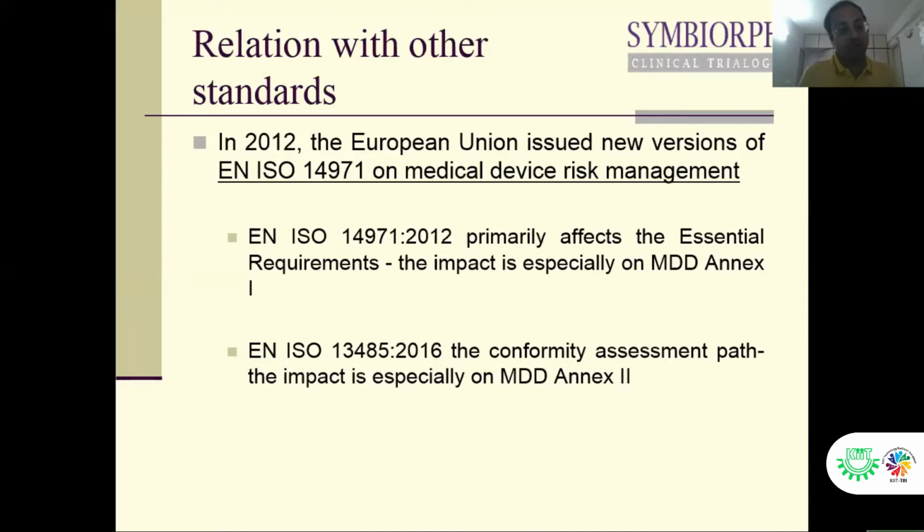And you have to prepare a separate document. You have to see that the risk-based approach on the process and on the product are two separate activities. Here I'm talking about the risk-based approach onto your system, not onto your product. So make sure that two different types of documents are prepared, one for your system, the risk-based system, and one for your devices.